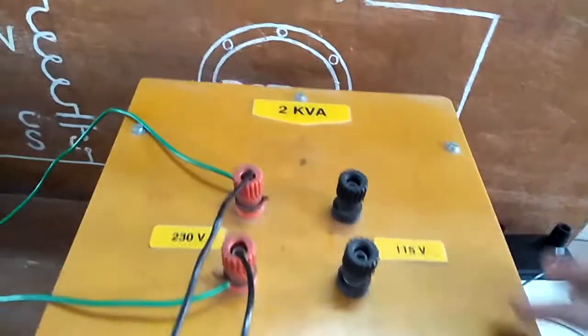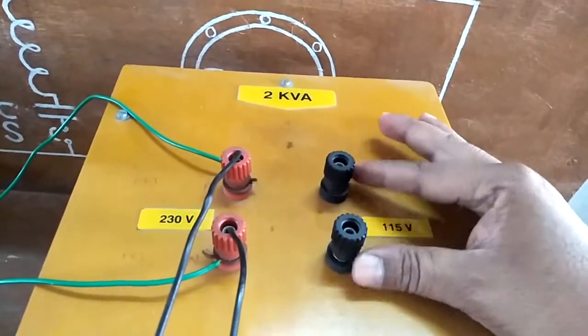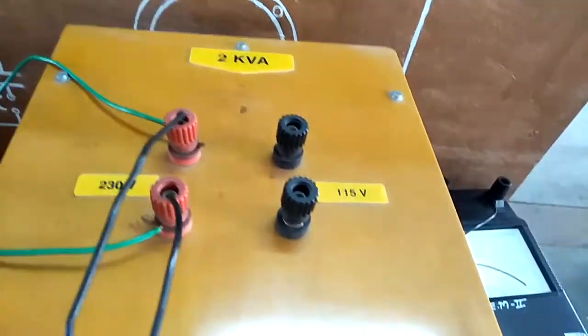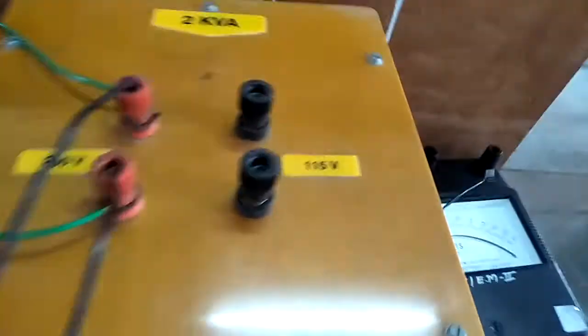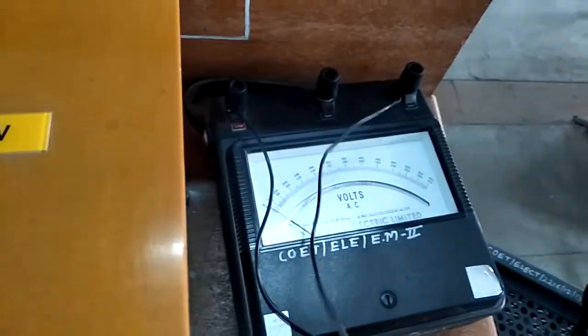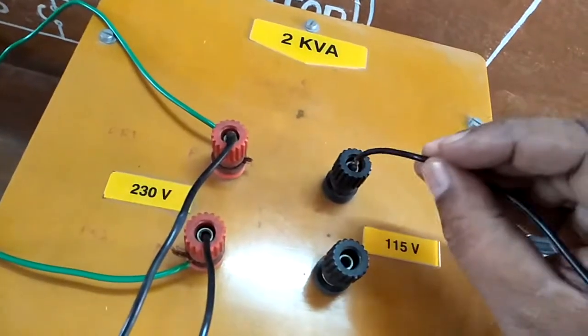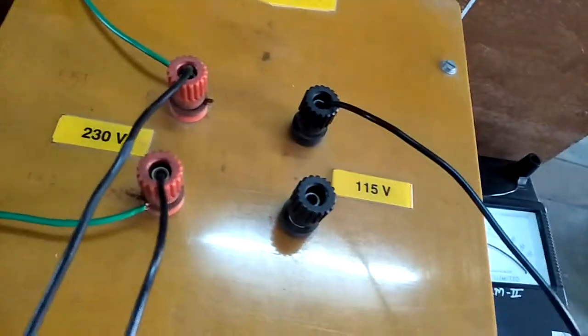Okay, so first of all we will perform the open circuit test, that is, the secondary side load is open. Here you can see the secondary winding is open. We are just connecting a voltmeter, an AC voltmeter 0 to 300, only to measure the secondary voltage, to check whether our transformer is working or not.